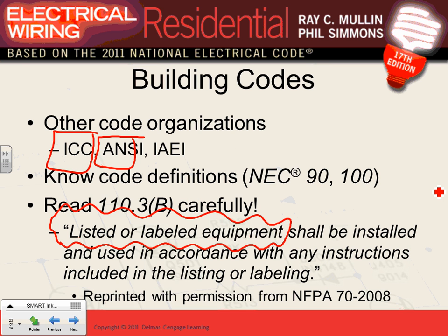This is directly from the NEC code book. Your equipment, before you install it, has to be listed by a third-party verification, as well as labeled - a label attached to it saying, yes, this switchgear can handle a 50,000 amp short circuit, and we tested it as UL and put a sticker on it rating it for 50,000 amp withstand. I can't do that as an engineer even. That's why in the NEC code book, listing and labeling is a big deal, and equipment that's listed and labeled has to be installed and operated according to the listing and labeling.